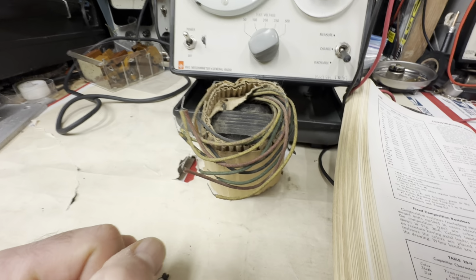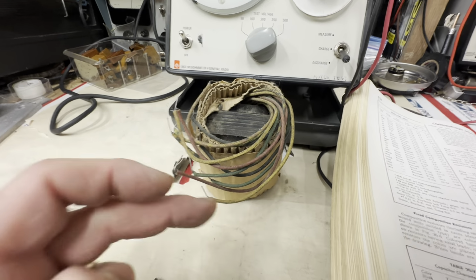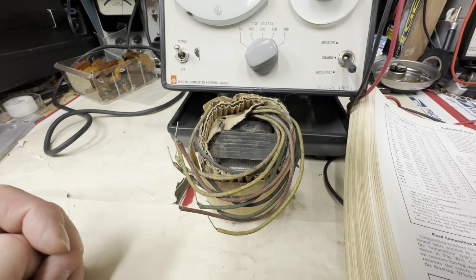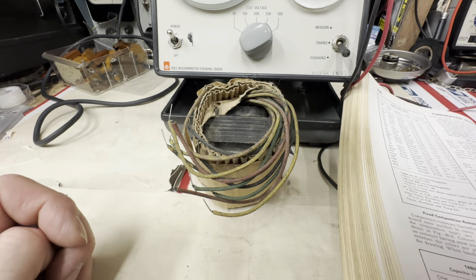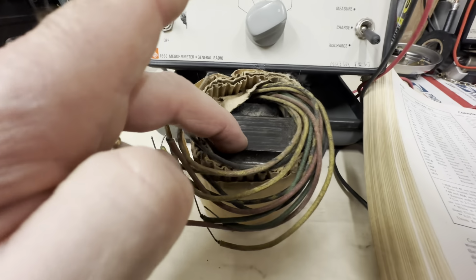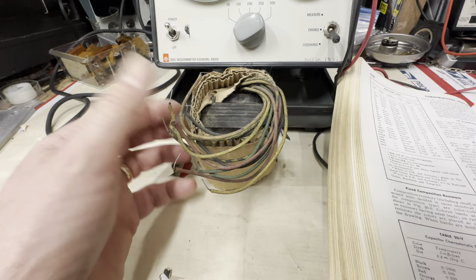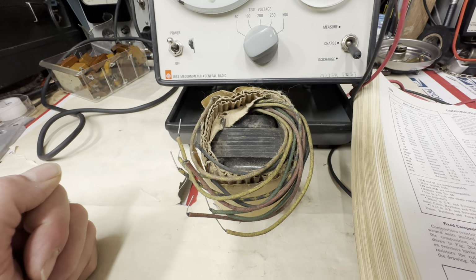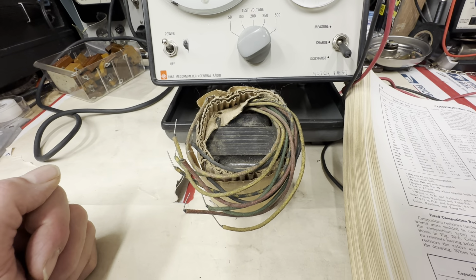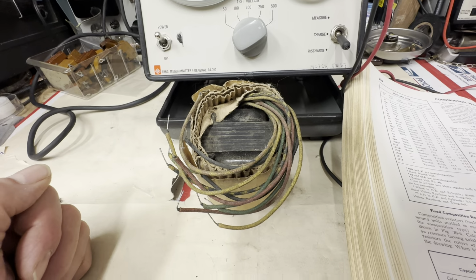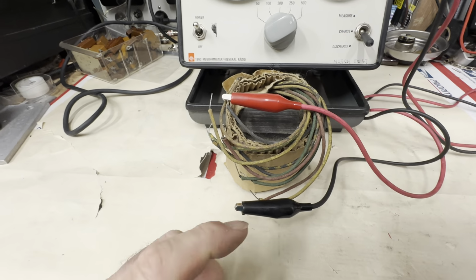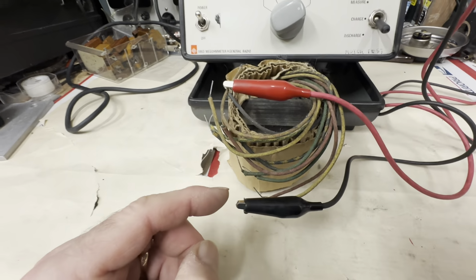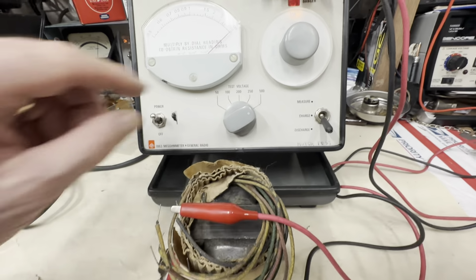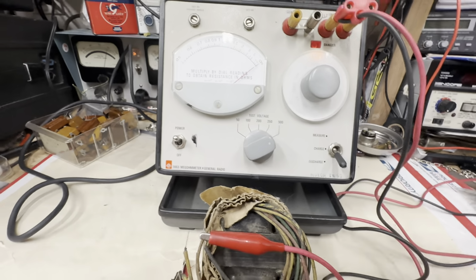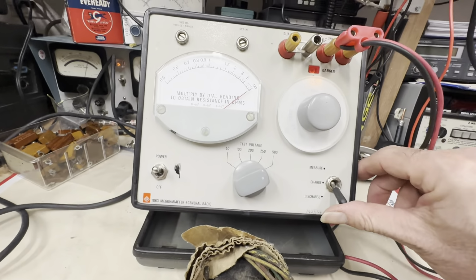So what we should be able to do with this is check between the windings here to make sure that there's no shorts. And if we have access to the case, we can actually clip onto the case to make sure that none of these windings are connected up to the case. But we'll check the windings here real quick. Okay, we checked here between the high voltage winding and the input. So let's go ahead. We're going to do 500 volts on this one. Started at a megohm down here.